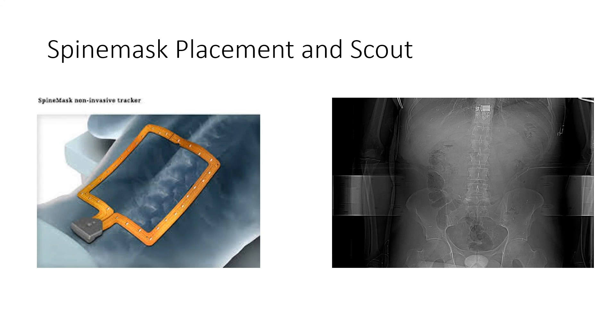This shows the spine mask and how it's used — it sticks to the patient and has both the fiducials and the transmitters in place. This shows a BodyTom scout where you can see the little fiducials. When you run the BodyTom, you can scan as much or as little of the spine as you want. As we get into more percutaneous screws, the BodyTom is very useful — with percutaneous screws under fluoroscopy, the amount of radiation is even higher than the other data I showed you.